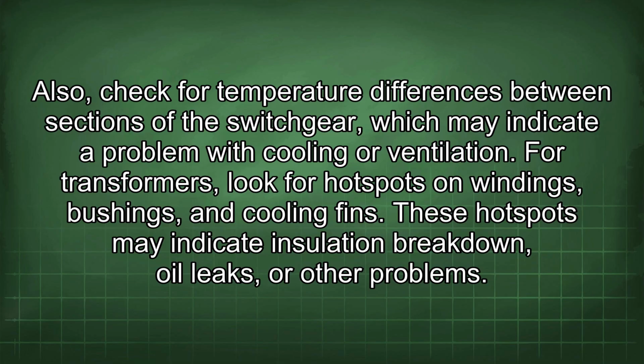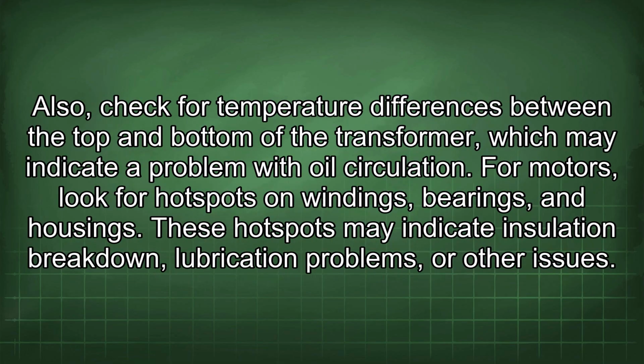For transformers, look for hotspots on windings, bushings, and cooling fins. These hotspots may indicate insulation breakdown, oil leaks, or other problems. Also, check for temperature differences between the top and bottom of the transformer, which may indicate a problem with oil circulation.